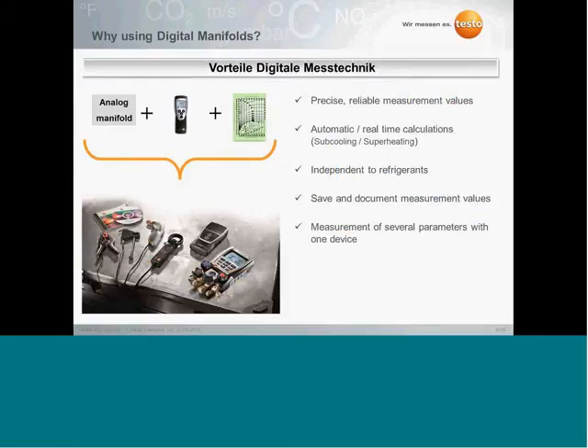Let's go to the next point. What are the advantages of digital measuring technology compared to analog technology? First of all, it is very precise and very reliable. I will come back to this point later in the presentation to give you a better overview. Next, you have an automatic and especially real-time calculation of subcooling and superheating. That means with an analog gauge, for example, you have to measure again if you want to see how a system develops when you change the setting of the system. The digital manifold measures constantly.